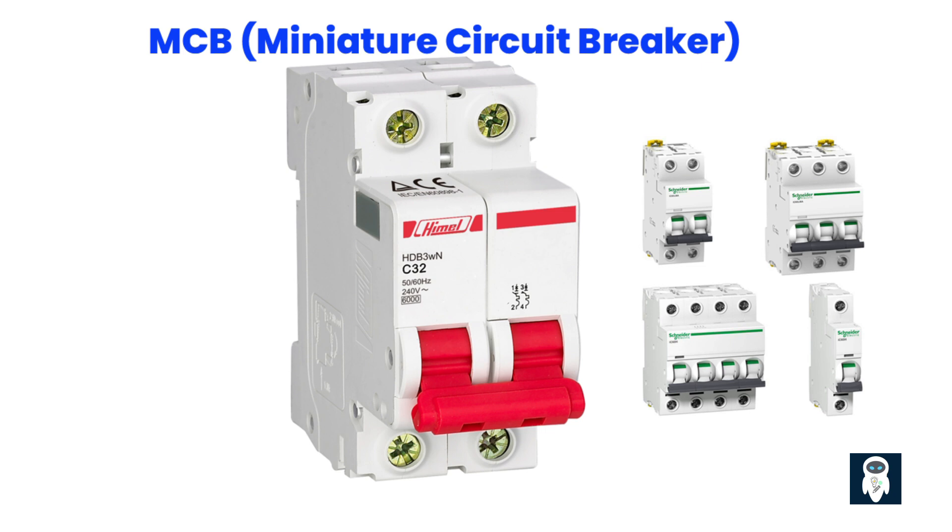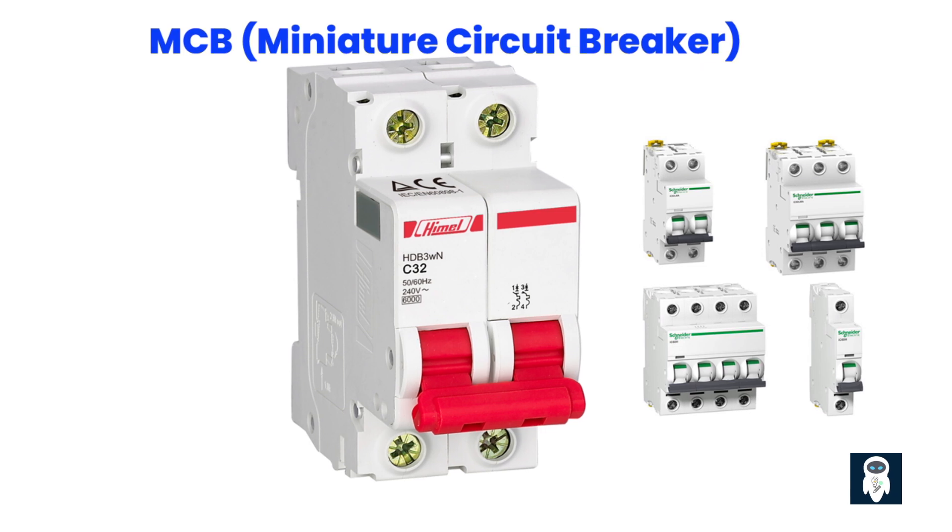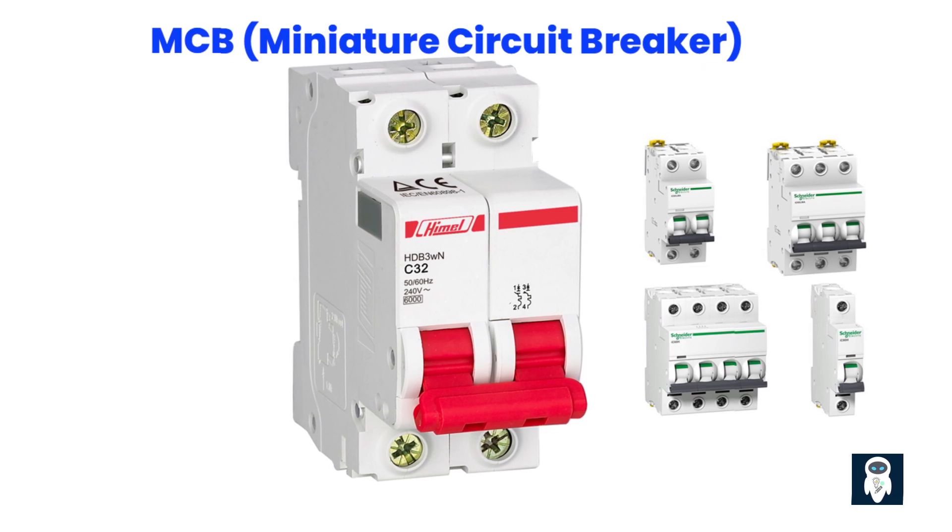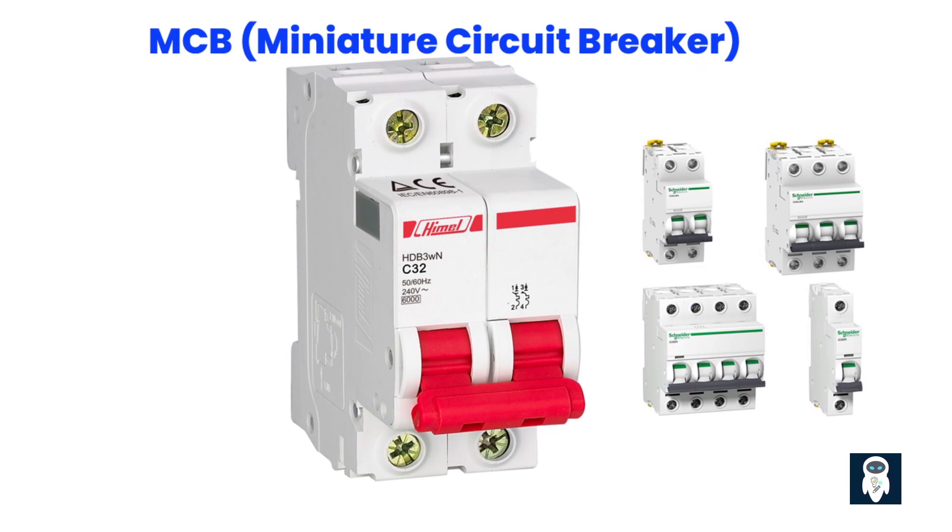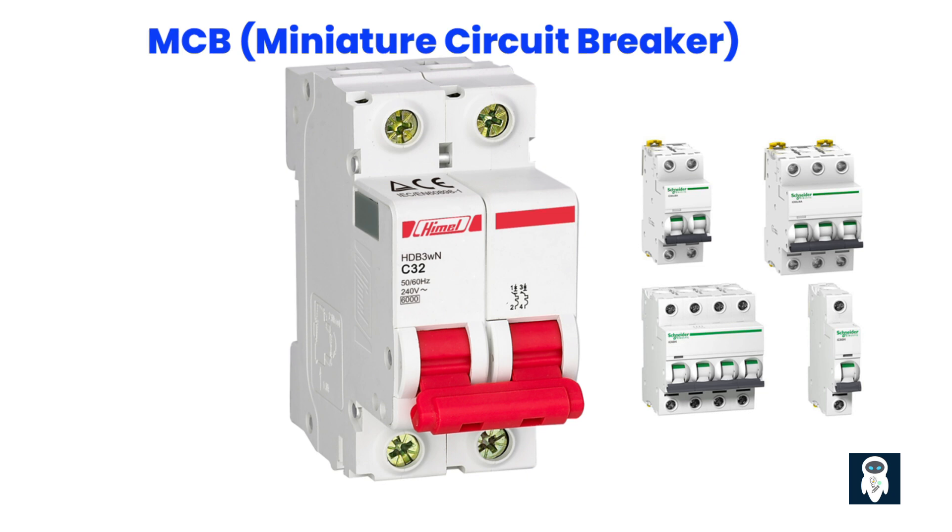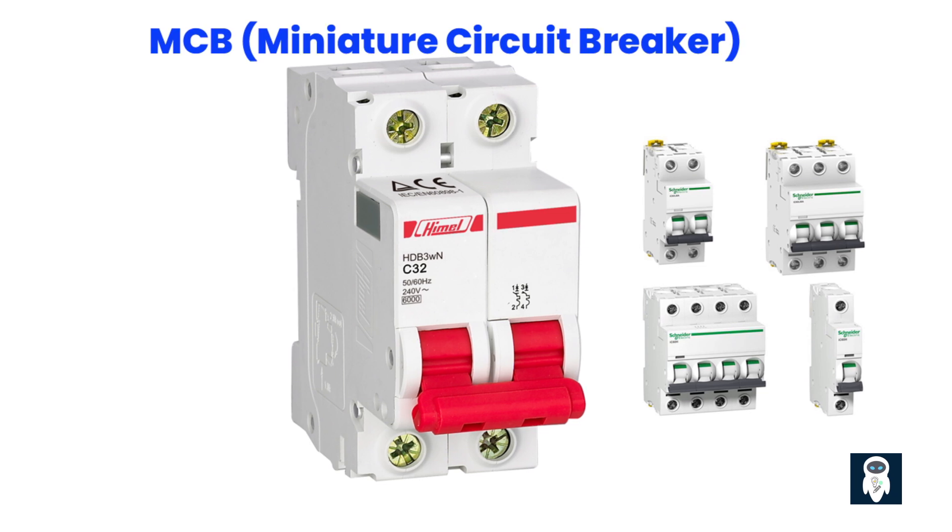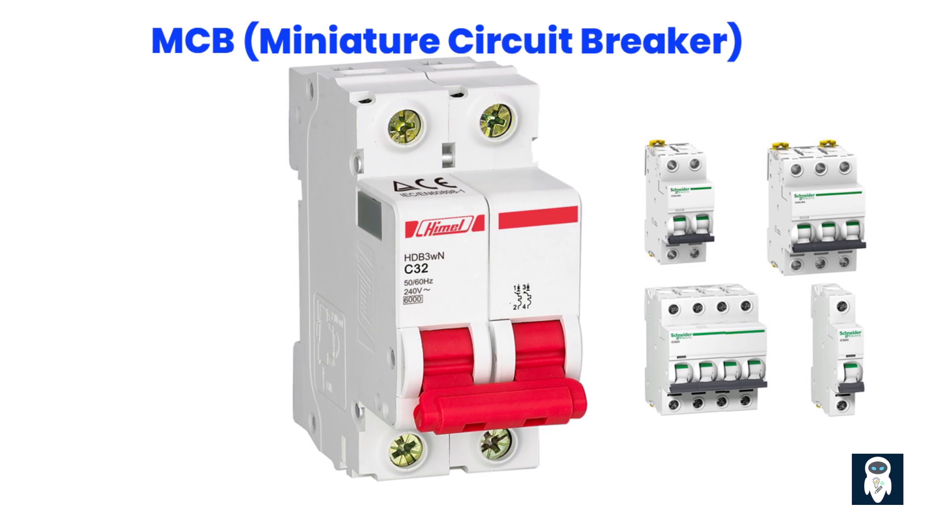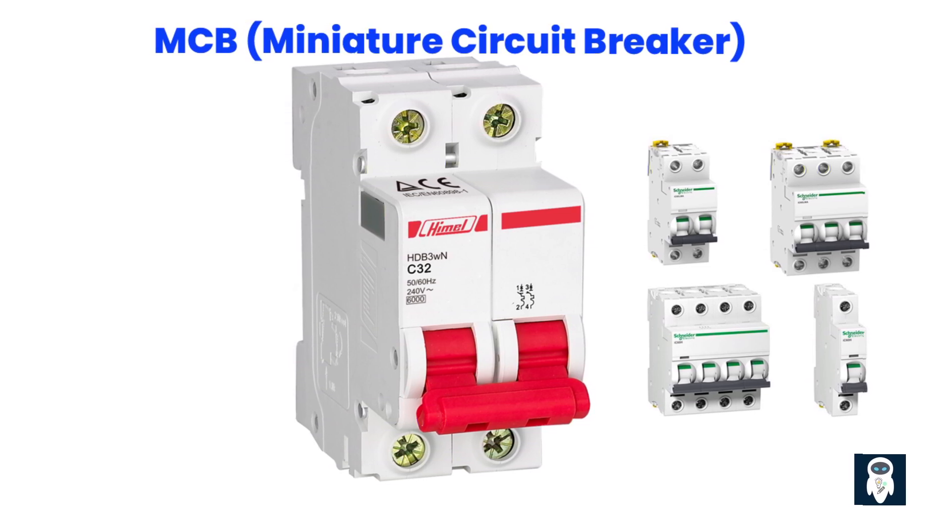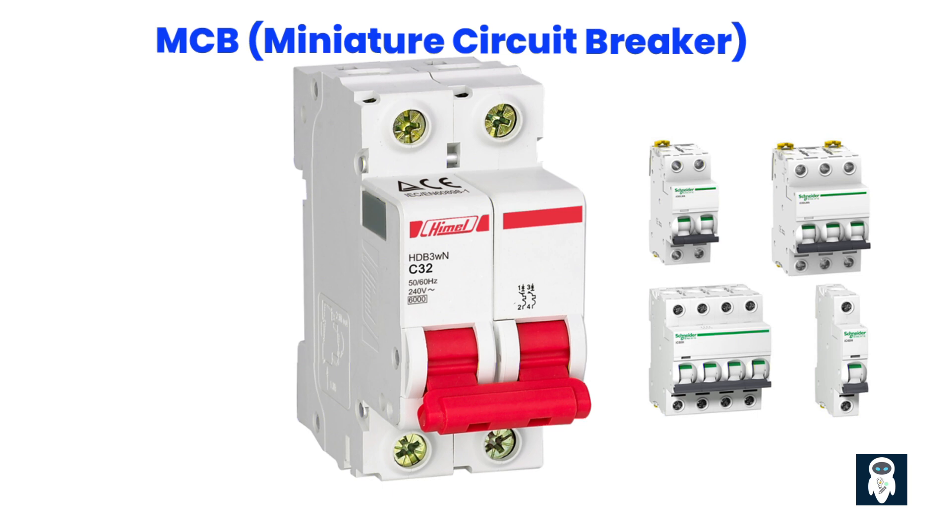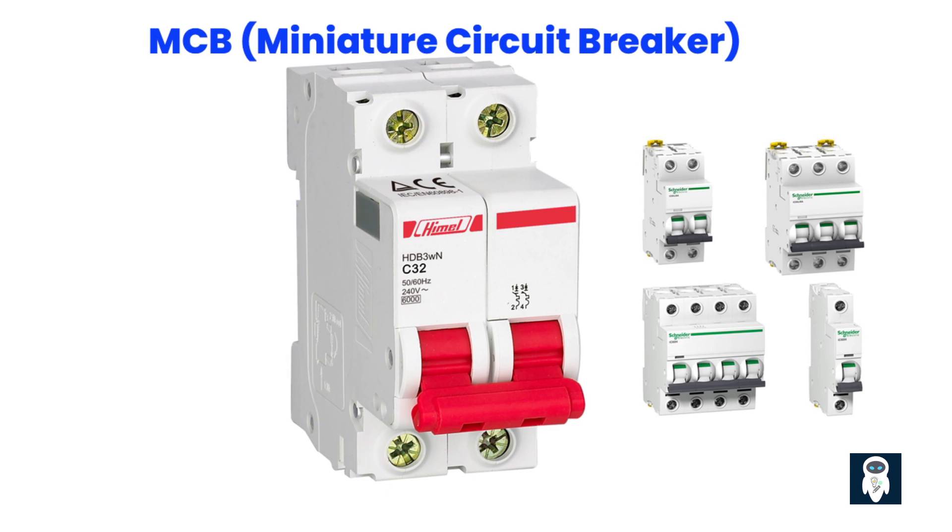MCBs stands for miniature circuit breakers. They are electrical devices designed to protect electrical circuits from overcurrents and short circuits. MCBs are commonly used in residential, commercial, and industrial electrical installations as a safety measure. When an electrical circuit experiences an overload or a short circuit, the current flowing through the circuit exceeds its rated capacity, which can lead to overheating and potential hazards such as fire or equipment damage. MCBs are installed in the circuit to detect these abnormal currents and interrupt the flow of electricity to prevent such incidents.